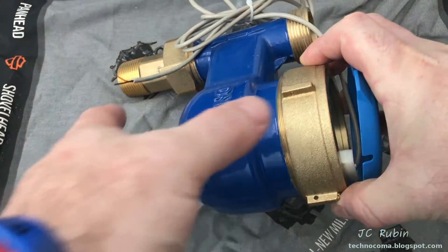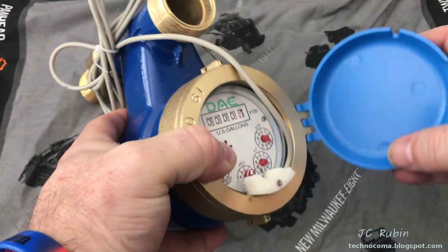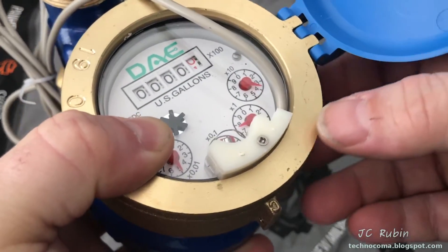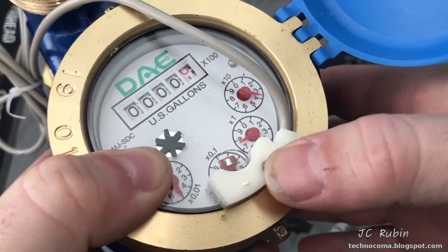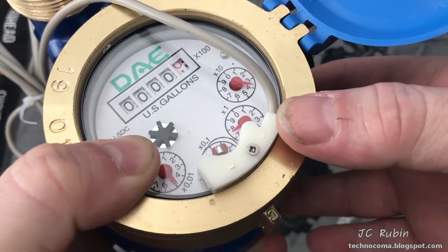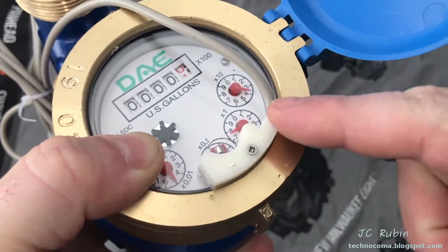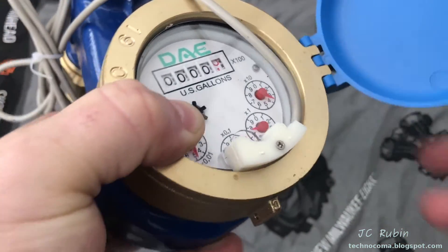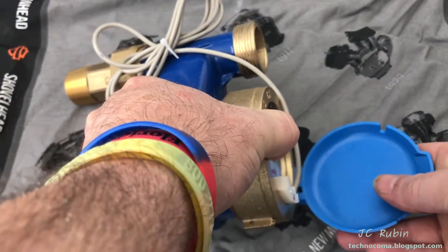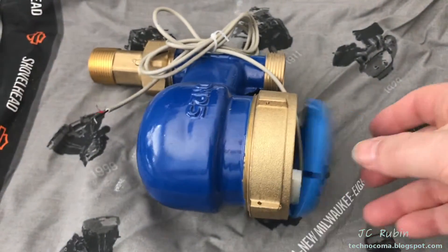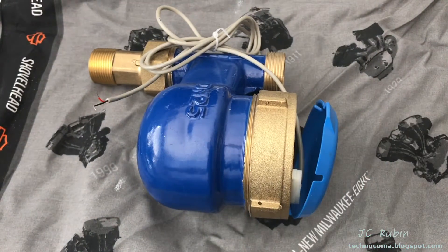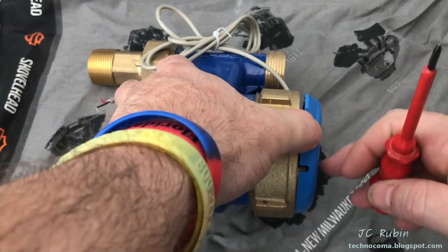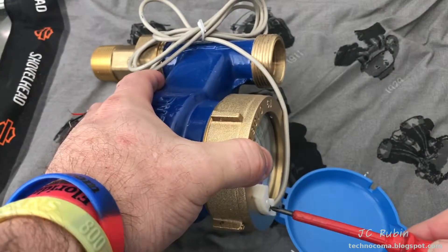The meter transfers the mechanical measurement of flow to digital measurement via a reed switch that's located right here in this white box. There's a magnet that circles the perimeter of this meter and every now and again that magnet will pass the reed switch and send a pulse that will allow us to record a certain amount of water flow.